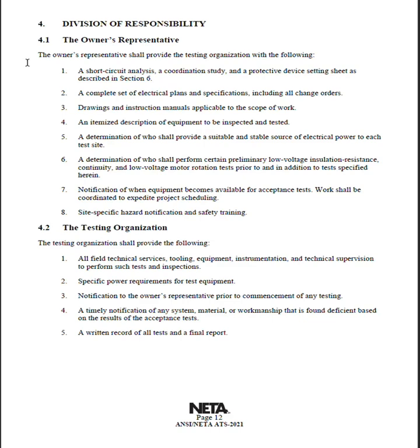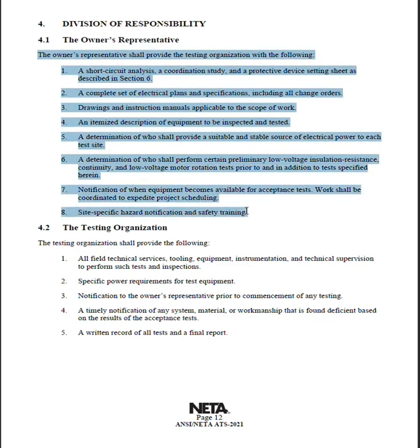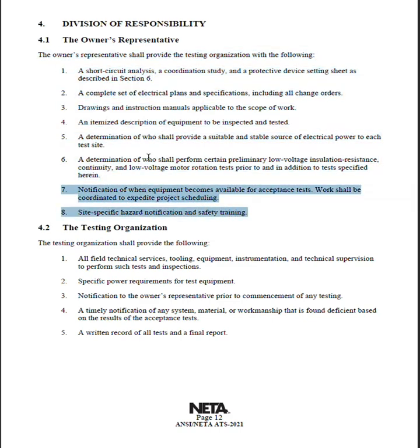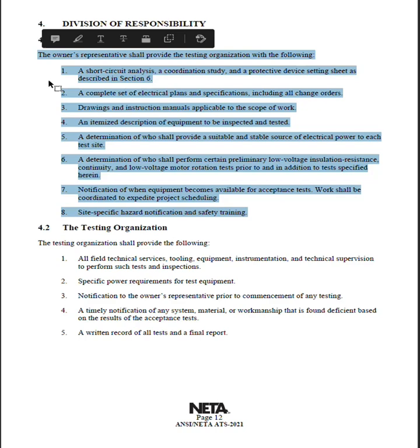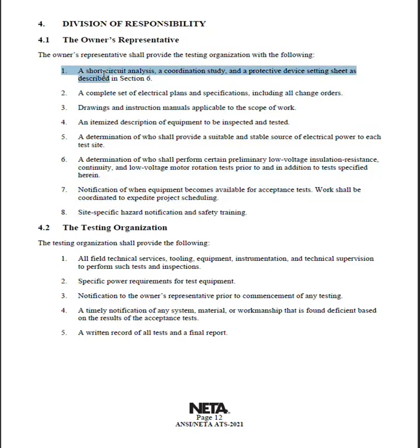Next thing, owner's rep. Sales guys, if you are out there selling jobs, you should be telling the owners that, oh yeah, we can test all your low voltage circuit breakers, but I'm going to need all of your protection settings. I need you to provide everything so that I can identify what to test your breakers at. And when I get done, or your electromechanicals, right? How many people go out there and test electromechanicals and you don't have previous settings, right? You don't have settings from the customer.